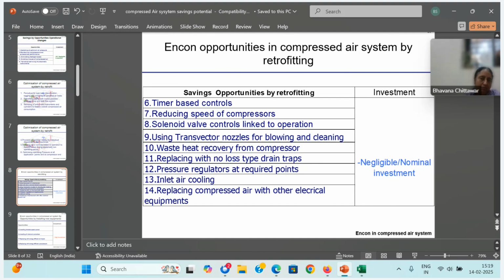Then pressure regulators at all points. Each and every application, and that's what I mentioned earlier, requires its own pressure and flow. So you have to study the pattern and control the pressure accordingly. The higher the pressure, the more your consumption will be. Sometimes high pressure damages the equipment also.